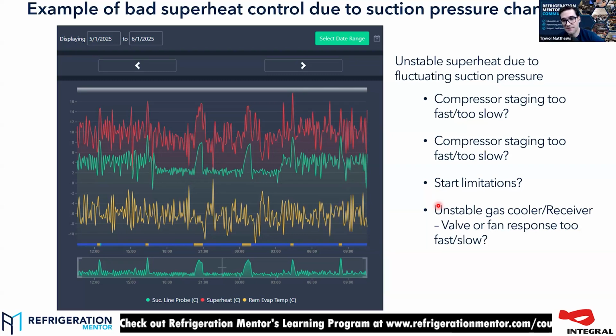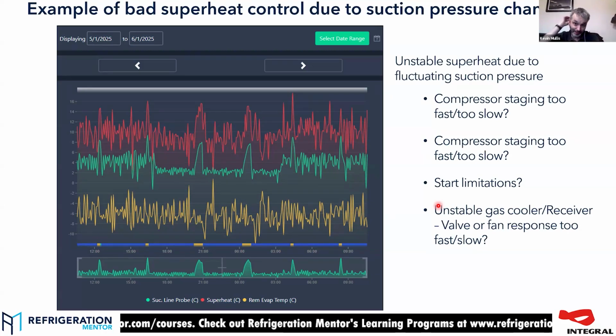Yep. It'll dump a ton into the receiver, which then gets dumped into the suction line, and you get a massive suction pressure spike. And your rack will be doing nothing for 5 minutes. It'll be madness for 3 minutes, and then you'll go through this cycle all the time. So don't go crazy high with it, and don't go crazy low with it. RDM do give you the option on this.